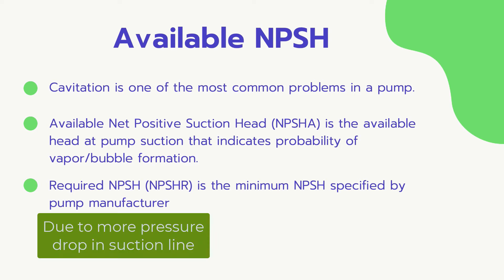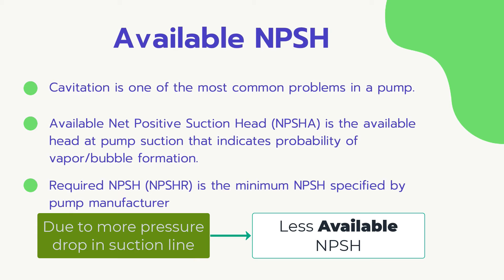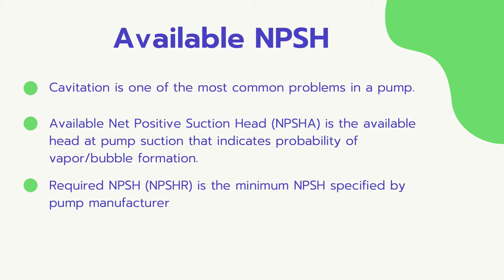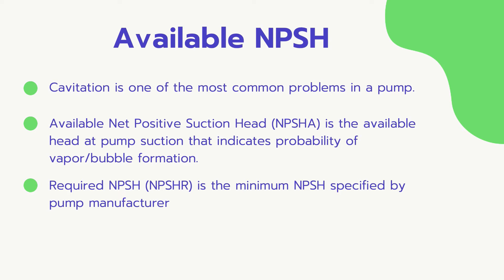In addition, due to increased losses in the system, the available NPSH would be reduced as flow rate increases. So as the flow rate increases, the probability of cavitation increases. This means that the NPSH available should always be greater than the required NPSH, and this should even be by a margin.